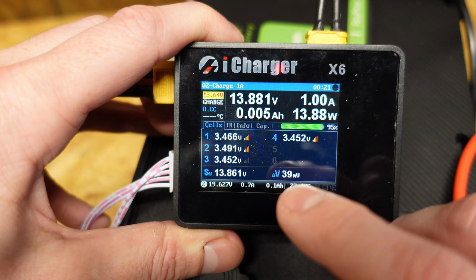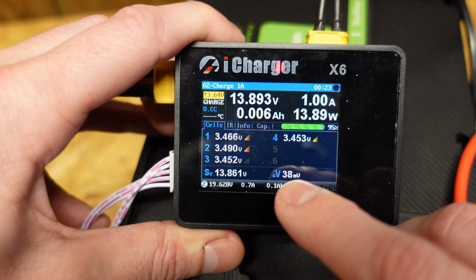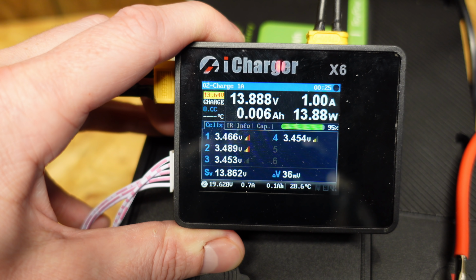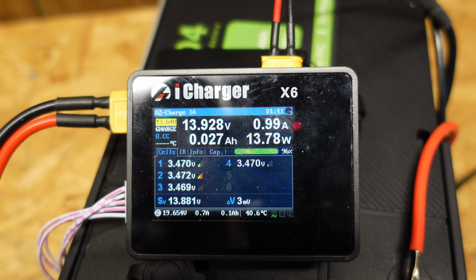You can see down here the difference between the high and the low cell sitting at 38 millivolts. Look how close together these voltages are now that this charger is attempting to balance them out - we're at a 1 millivolt difference while charging at 1 amp. That is pretty good. So we're just going to let this run and see if it balances out at the top end, and then we'll redo our discharge test once this has completed.